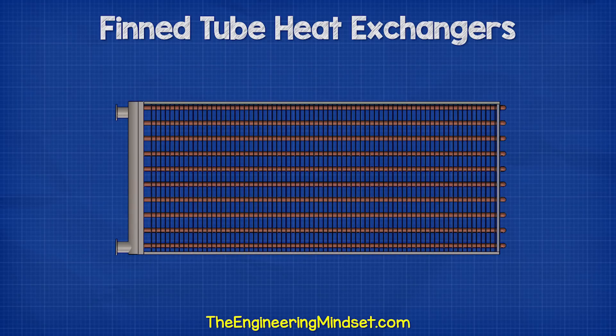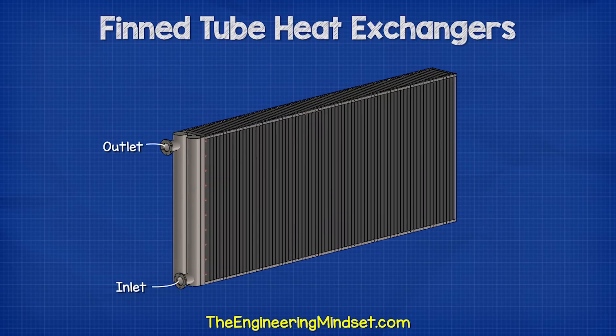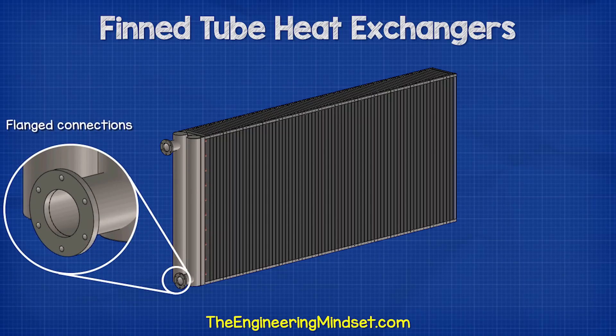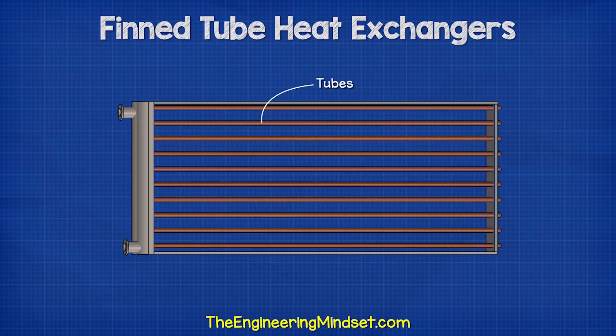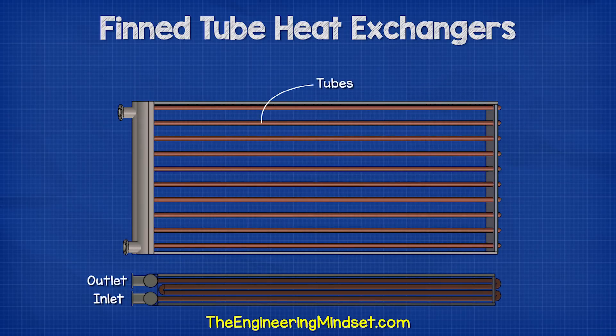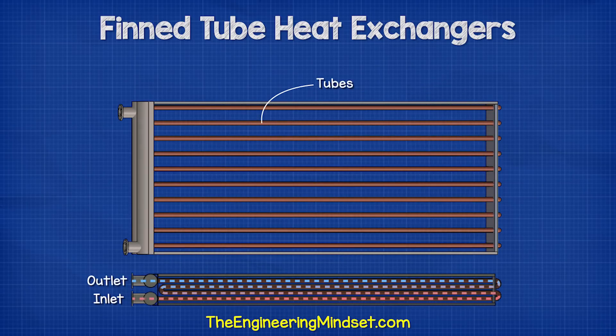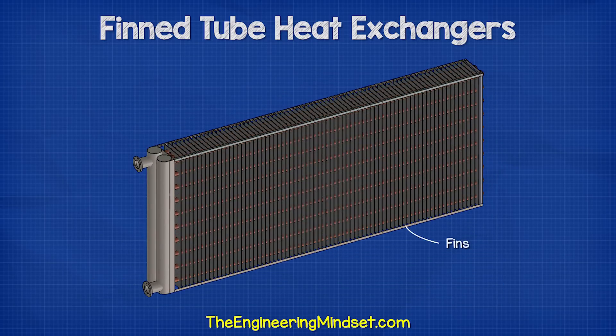A typical fin-tube heat exchanger looks something like this. We see there is an inlet and an outlet, both usually located on the same end. These connections are typically flanged, but they could be threaded or soldered depending on the application and the pressures of the working fluids. Running between the inlet and the outlet is a tube which will contain and direct one of the working fluids, for example, hot water.